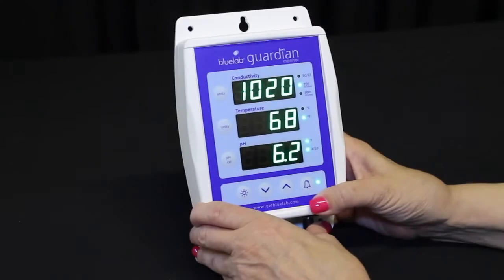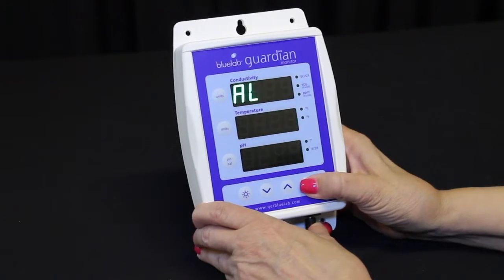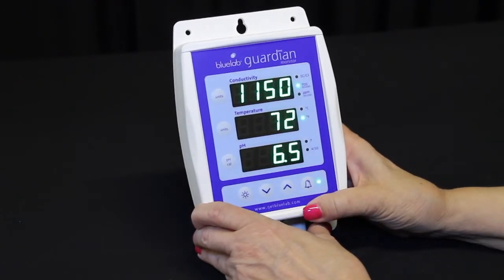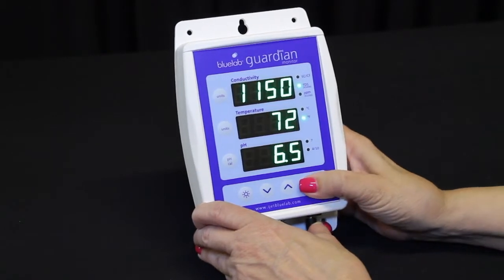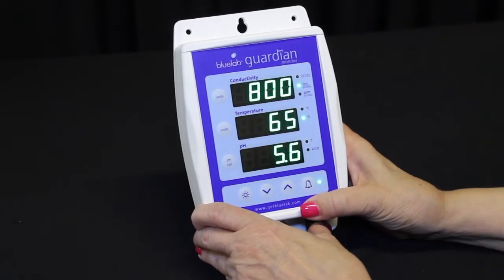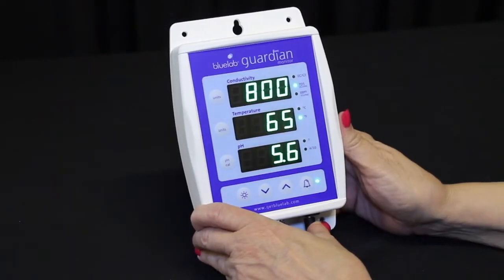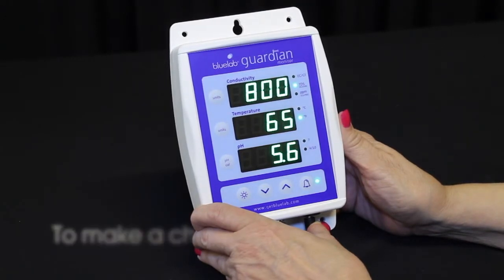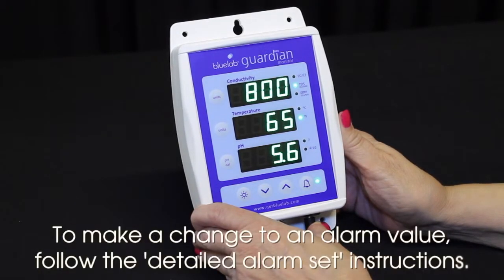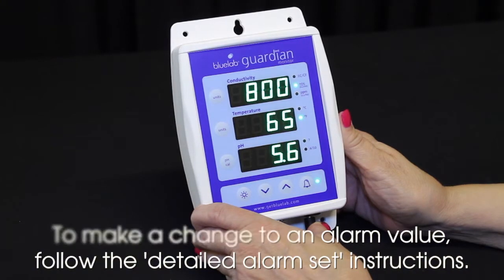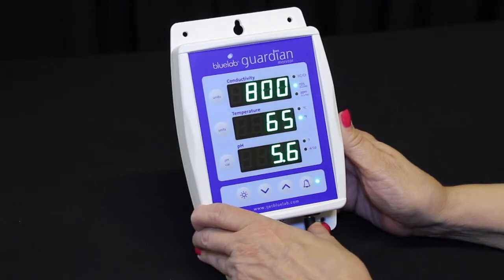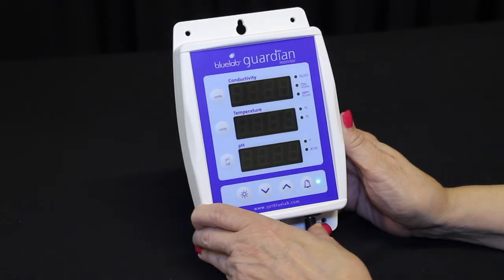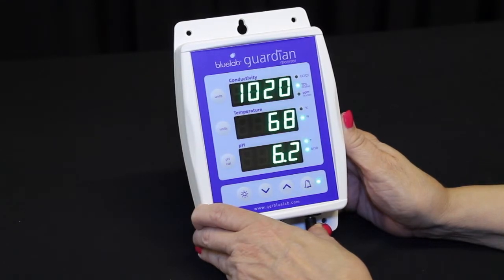To review your current alarm parameters without changing the values, long press the alarm button to view the high alarm values. Short press the alarm button to view the low alarm values. To exit the alarm settings mode without changing any values, avoid pressing any keys. After 15 seconds, the Guardian Monitor will exit the alarm settings and display no save before returning to its normal monitoring mode.